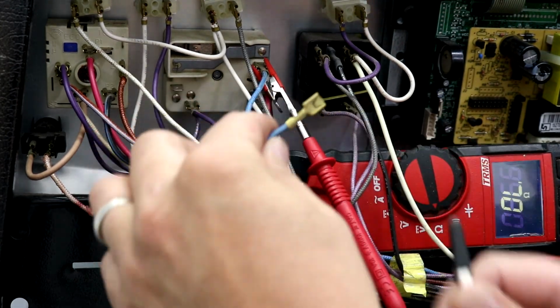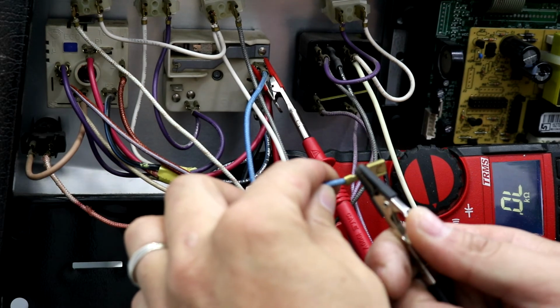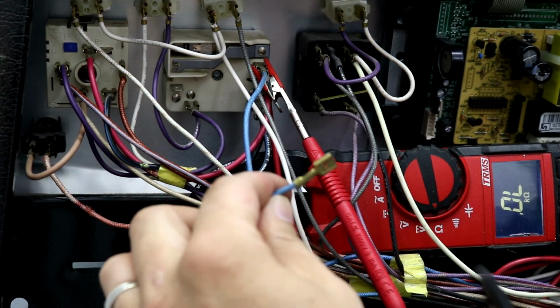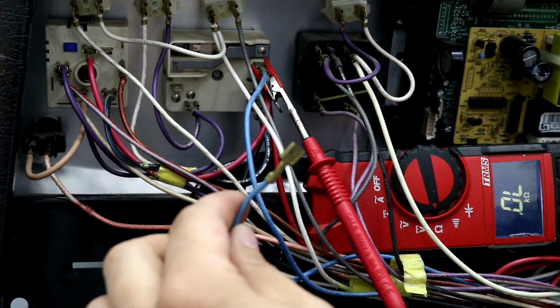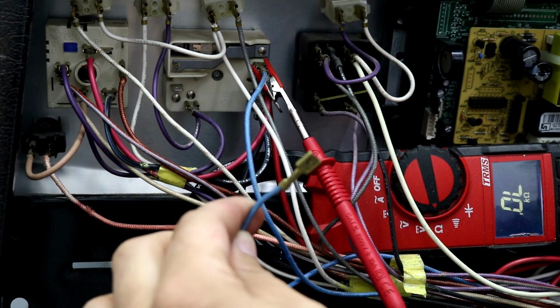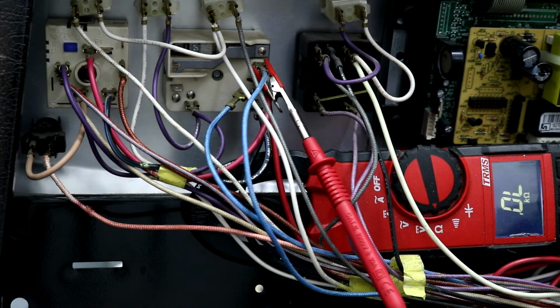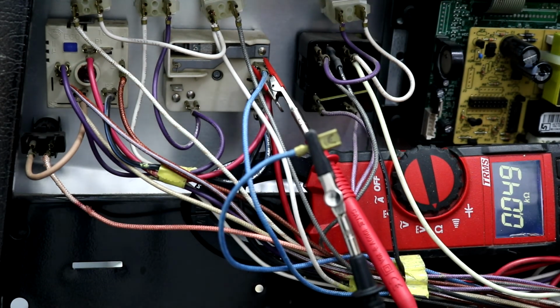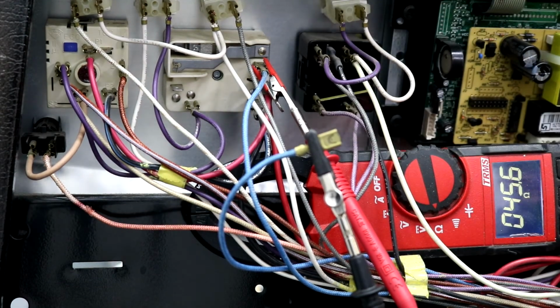Now if you get a reading like this, when you have this contact touching here, then either the high temperature probe switch is bad or the windings are bad on the element, and it would need to be replaced. But if you get a good reading like this, of about 45 ohms or so, and the burner's not lighting up, then the switch is bad and would need to be replaced.